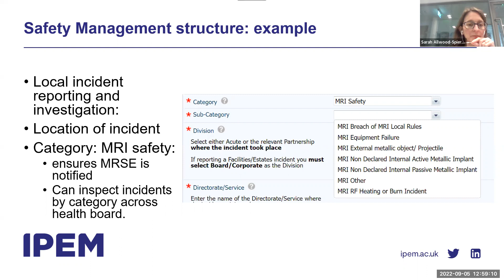Onto our annual safety audit now. For the acceptance testing of our radiotherapy planning scanner, the diagnostic MRI physicists, the MR safety experts, carried out a standard diagnostic acceptance test. There were then additional QA and acceptance tests carried out by the radiotherapy imaging physicists appropriate to radiotherapy. We have an annual safety audit that's carried out by an MR safety expert, and this is in place to test that the MHRA guidelines are followed, that safety-related documentation is up to date, and that the MR responsible person is supported in having enough time to carry out these tasks.